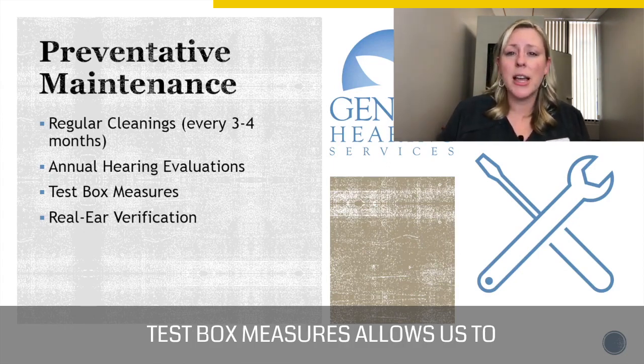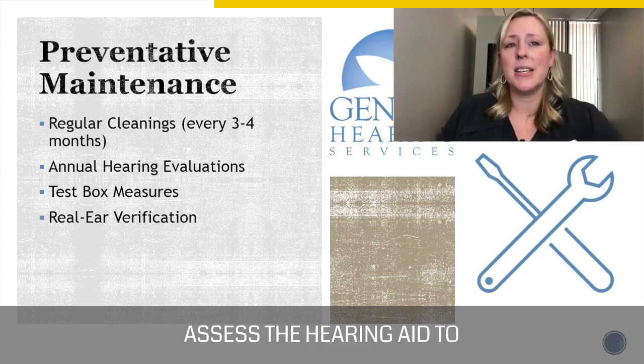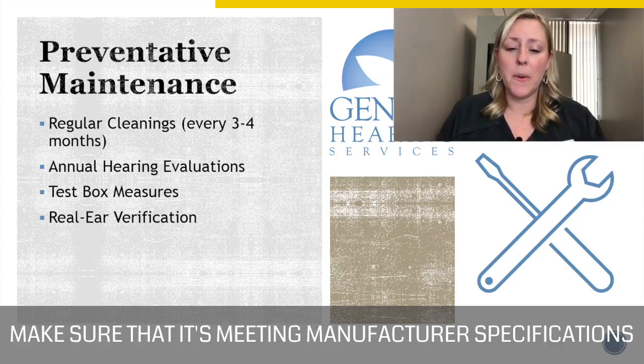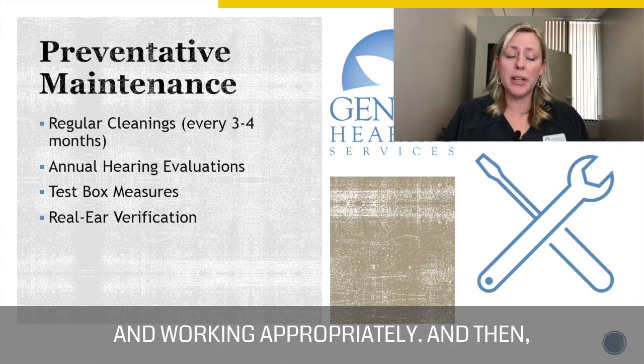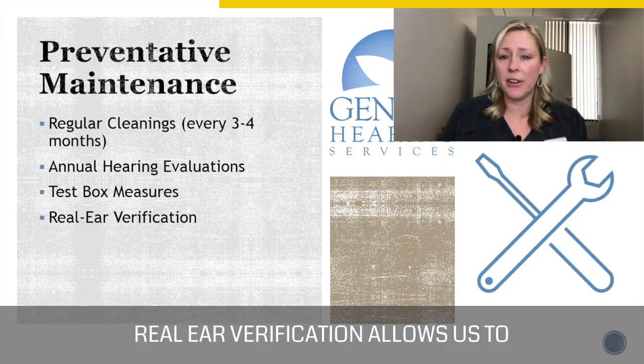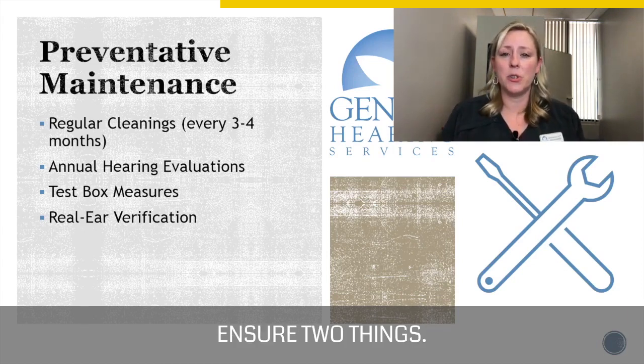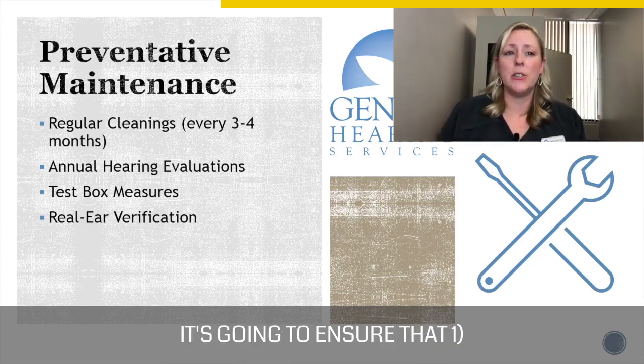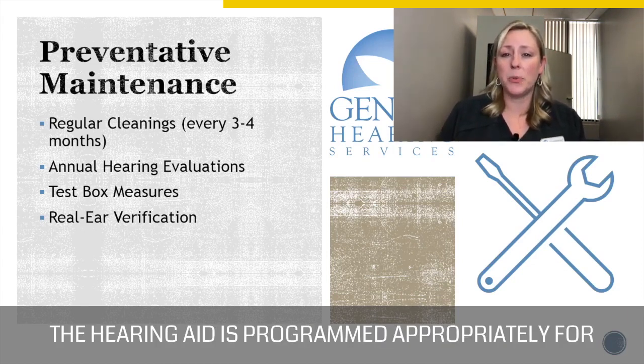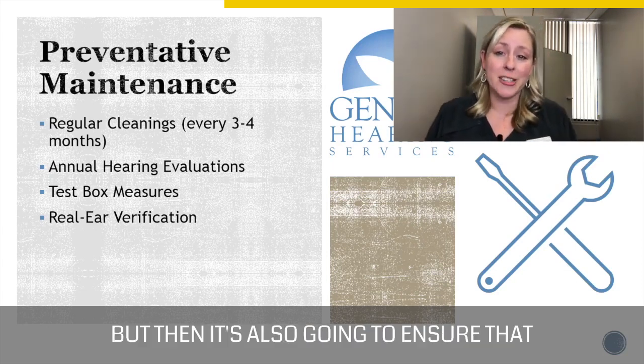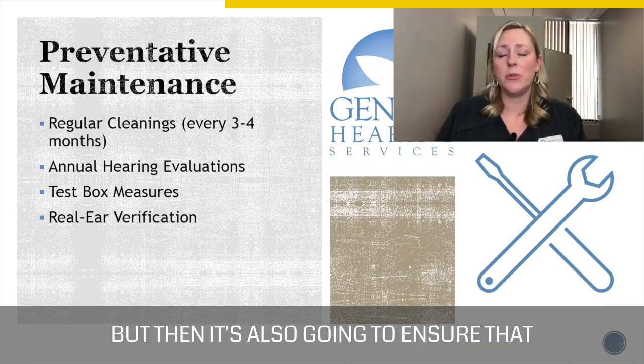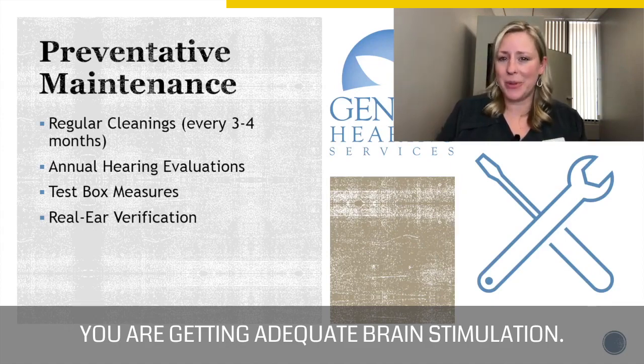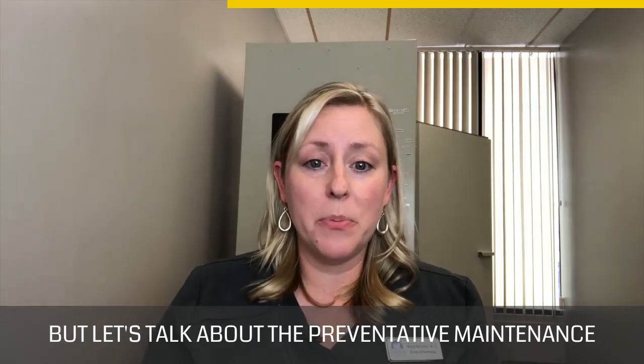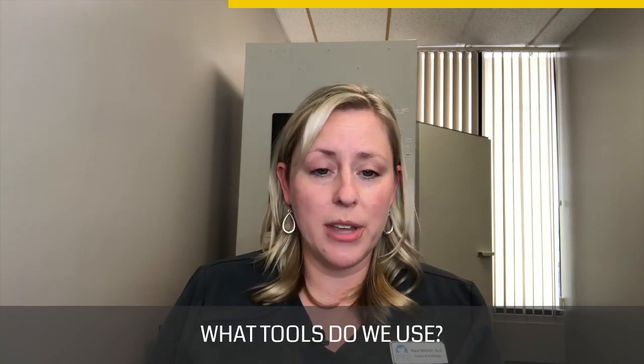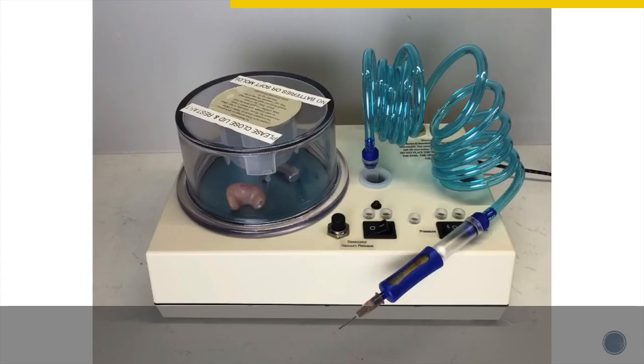Test box measures allow us to assess the hearing aid to make sure that it's meeting manufacturer specifications and working appropriately. And then of course, real ear verification allows us to ensure two things. One, the hearing aid is programmed appropriately for your hearing loss, but then it's also going to ensure that you are getting adequate brain stimulation. But let's talk about the preventative maintenance and how we do that. What tools do we use?